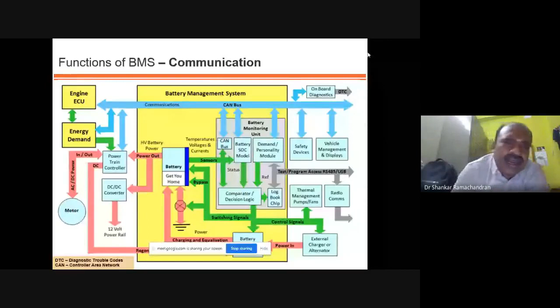Another part of BMS is battery connection to the load, the function which is taken care of by the BMS before connecting it to the load. There is a pre-charge resistor. In most battery systems, the load and the charger have high capacitance at the high current side facing the battery. High current levels for extended periods of time can definitely damage the system, where the connection contacts may get welded. That is why these pre-charge resistors play an important role in controlling the inrush current.